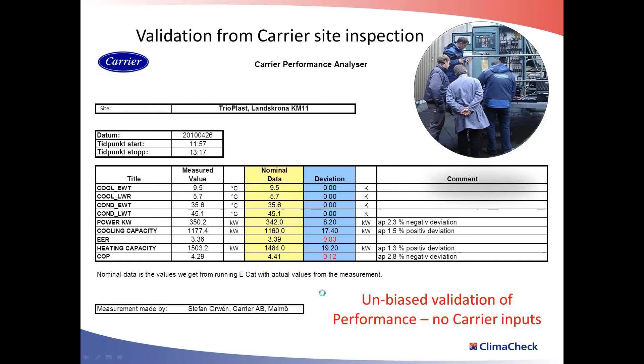And there are many advantages with measuring on the refrigeration process. I mean, it's a very well-defined system, and the properties of the refrigerants are well known and defined. And you can connect it in 20-30 minutes, and this method becomes very insensitive to measuring errors. It's not like when you measure on the water side, where you have a few degrees temperature difference, which makes any error very, very significant.